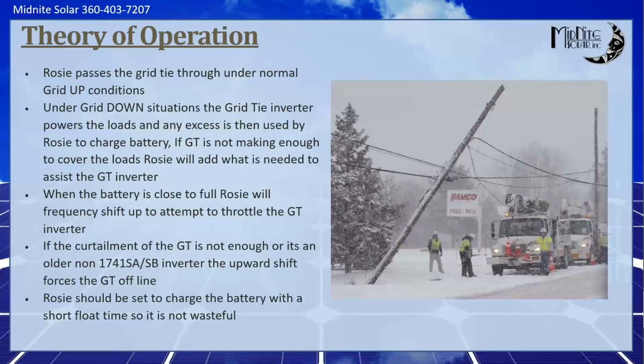until it gets to the one that forces it offline. The Rosie should also be set to charge the battery for a short float time. This is another one. You don't want the Rosie floating 24/7. This is sort of true of any grid-connected Rosie system. In the battery config menu, you'll find a float time which defaults to 24 hours. You want to set that down to something more reasonable, like 1 or 2 hours if you're grid-connected. Now, that doesn't affect the charge controllers. If you're DC coupled, the charge controllers will float all day long as there's sun out. But what that does, it allows the Rosie's charger to go silent and quit buying power from the grid. So that's another little thing to check.